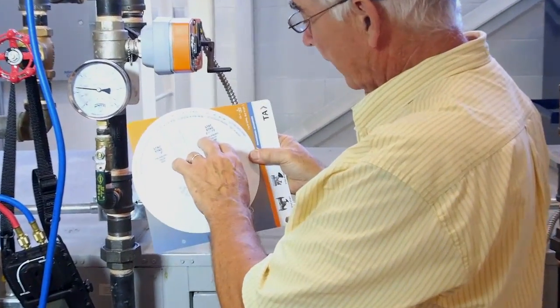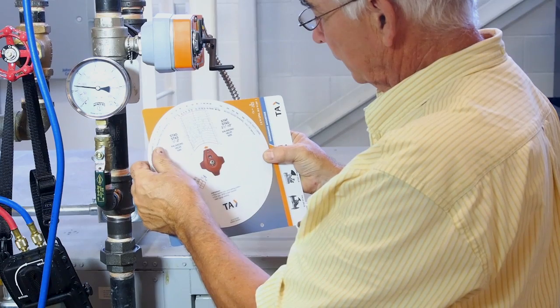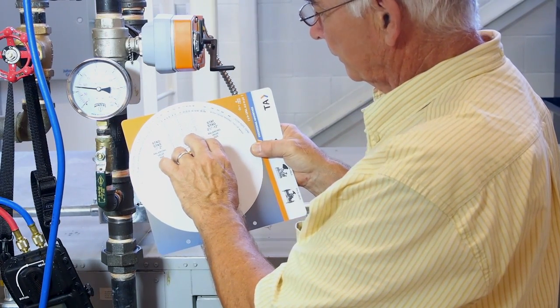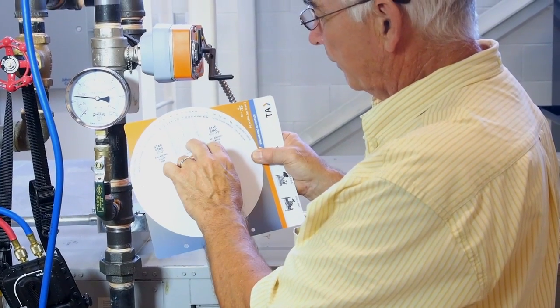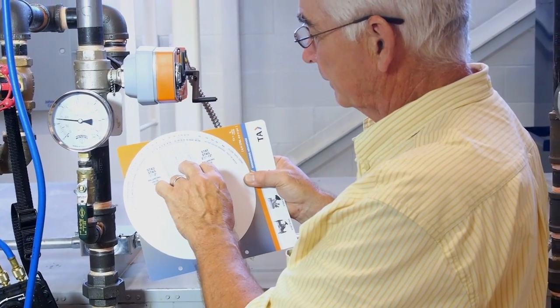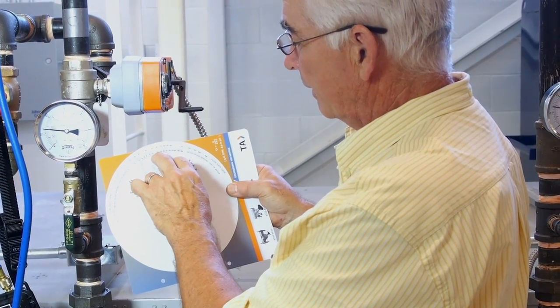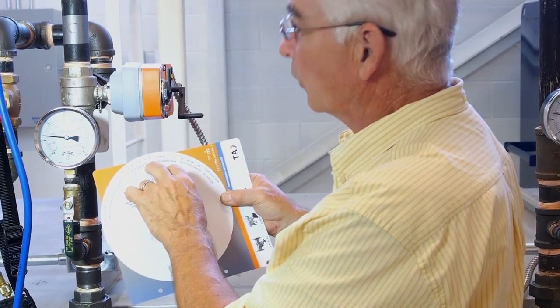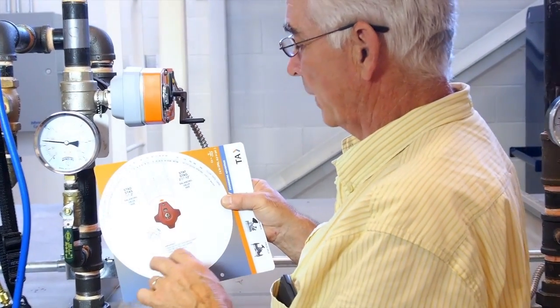The one and a half inch circuit balancing valve, if we measure pressure of ten feet, that would be forty-eight gallons if it's wide open.